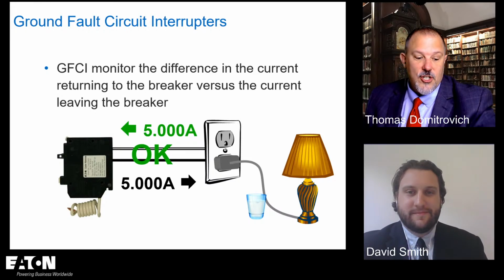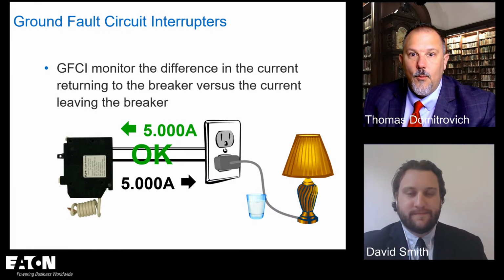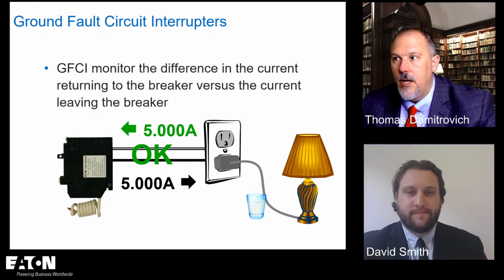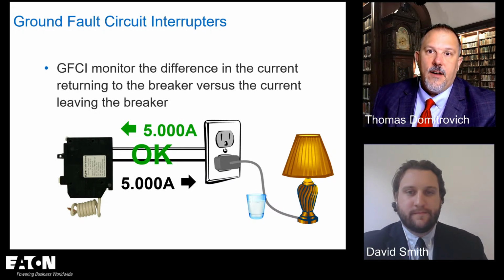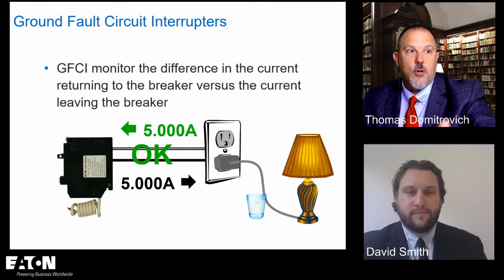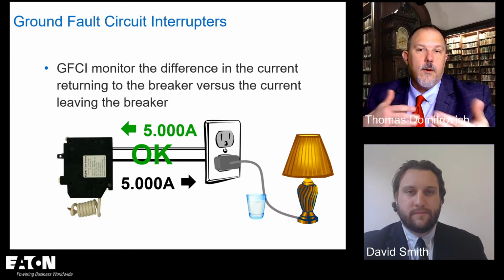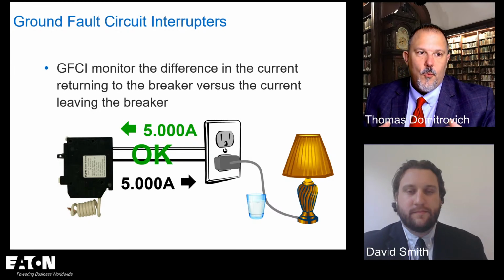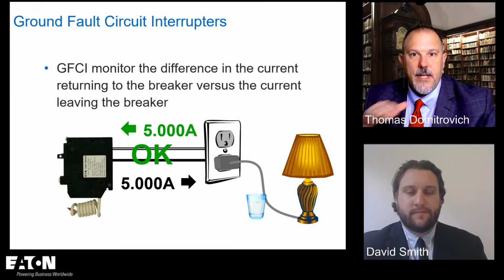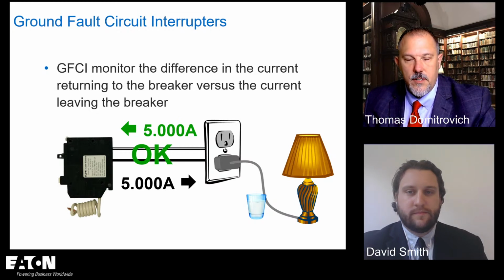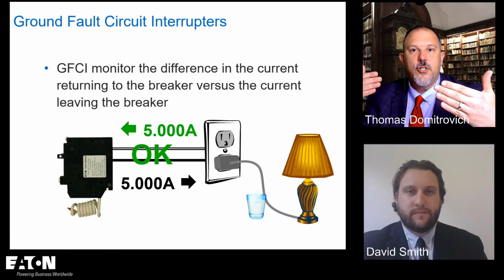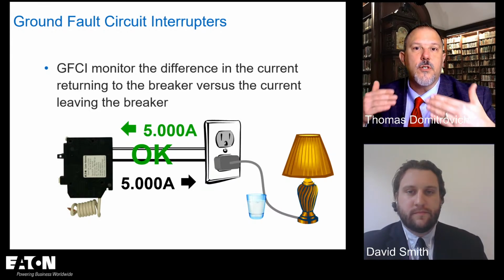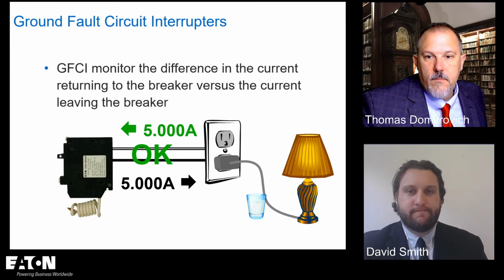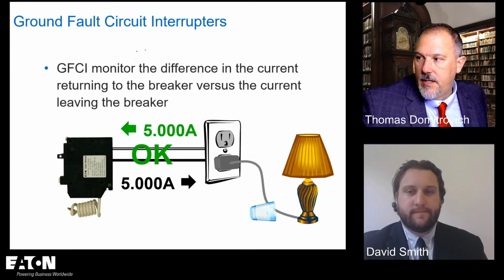So then the challenge would be, well, I would have put a GFCI circuit breaker in there. What about if I had a GFCI receptacle feeding that, where would I put my AFCI? So we're going to talk about those different configurations as we get into the National Electrical Code. But the first step in all of this is to understand there's no compatibility issues between a GFCI and an AFCI. They can be on the same circuit. There's no compatibility concerns. No one's doing the other's job. They both focus on something different.